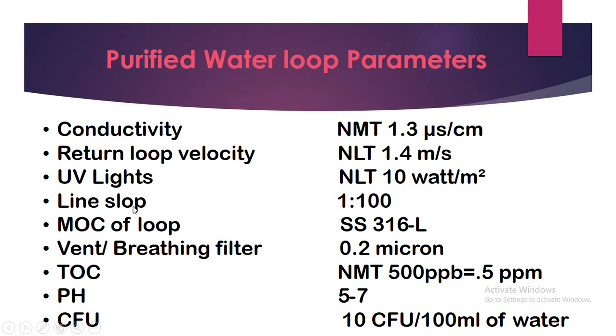The loop pipe should have a slope — a ratio of 1 in 100 — so that water drains automatically by gravity. The material of construction (MOC) of the piping and storage tank should be SS316L grade. The vent or breathing filter size should be 0.2 micron.